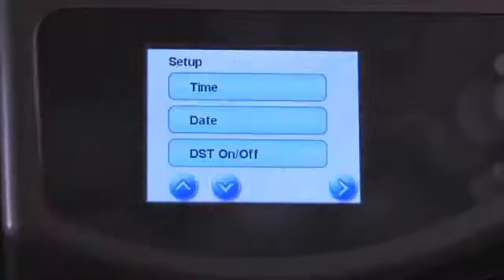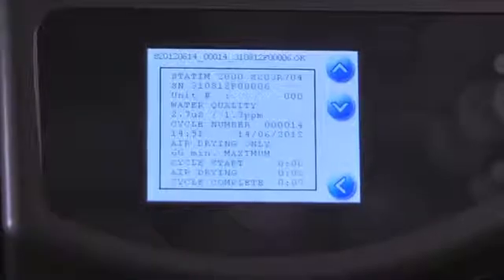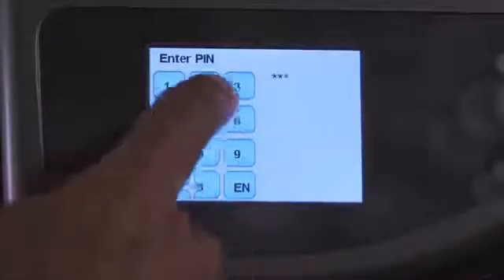Should the completion of a sterilization cycle ever be in question, the last five cycles are available to view directly from the color LCD screen. While the STATIM G4 is designed for ease of use, if clarification on any aspect of operation is required, instructional tutorial slideshows are available to view on the bright, high-resolution touch screen. The G4 also protects patient safety with a verifiable, pin-protected process. The latest generation of STATIM has been modernized with a new, sleek, and contemporary look, complemented with an optional matching silicone stat mat to protect and keep the unit looking brand new for years.